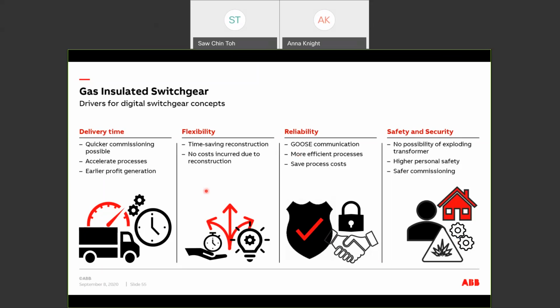The installation and commissioning time can be improved as well due to the lesser interpanel wiring and also fewer low voltage components to be tested at site. This also will reduce the possibility of errors and failure at site. Hence, digital switchgear not only speeds up the delivery of the switchgear, it also speeds up the site activities, and the project can start to generate revenue for you quicker.